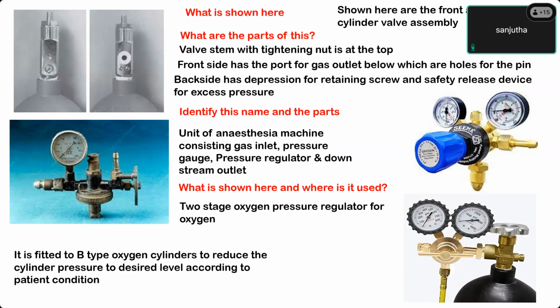Cracking the cylinder. This is the wheel handle for opening the oxygen. If you rotate it by holding it on the top, it will open the oxygen, and you can see the different pressures. One has pressures of 1000, 2000, 3000, 4000, and another has 100, 200, 300, 400, like that, pounds per square inch, or PSI rather. Instead of a plastic knob, it has a lever-like thing. By rotating that, you can adjust the pressure in both. So this is one of the very old equipment. I have just kept it in case some hospitals may still have this. You should not be taken by surprise by not knowing what they are for.